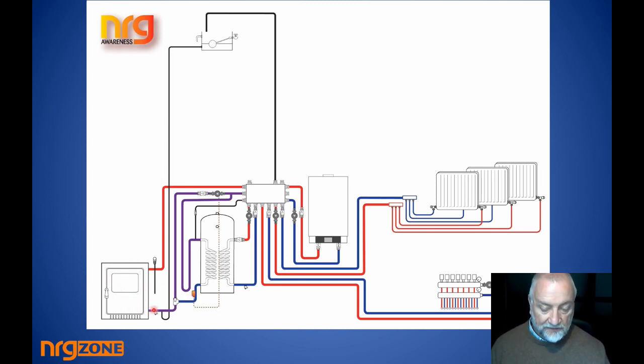There's two reasons for that. One is the back end burnout, where the stove will form acidic flue gases, will condense onto the surfaces and damage it. But the second is you want to keep your flue gases hot enough so that they'll convect out of the chimney and away. If you take too much heat out of the stove and the water is cold, the smoke will have no potential to rise. If it has no potential to rise, it can lodge in the flue on the way up or start to drift very slowly.